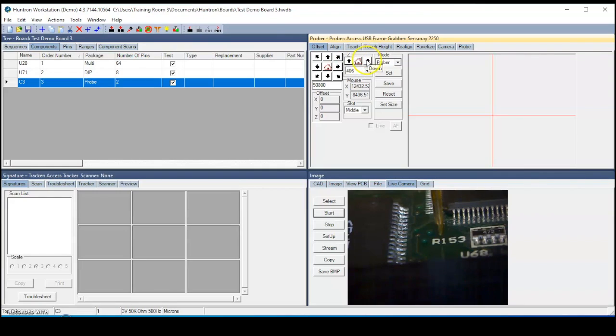Okay, you saw it just lift. Let's kick it back down, and now it's just making contact. You can see that it's not on our target, so we need to move it to the left. So to do that, we'll use the arrow keys. I'll go 100 microns at a step, and the probe will lift as I move it sideways. So it'll take me several clicks to get this over on the target. We want to get it precisely on that same target that we selected with the camera. And one more click. That looks pretty good.